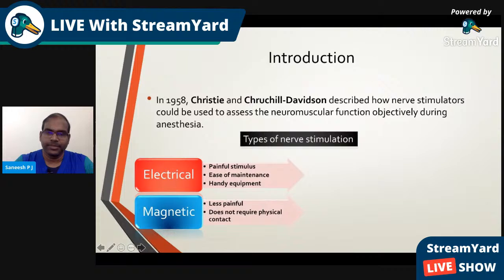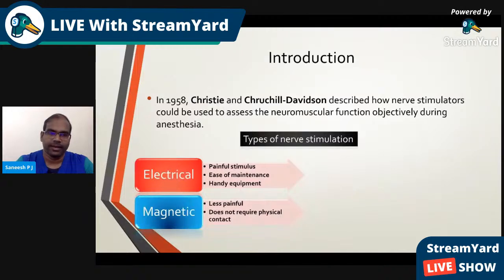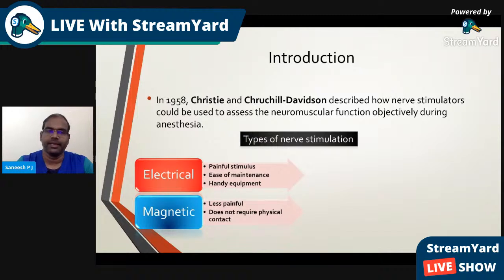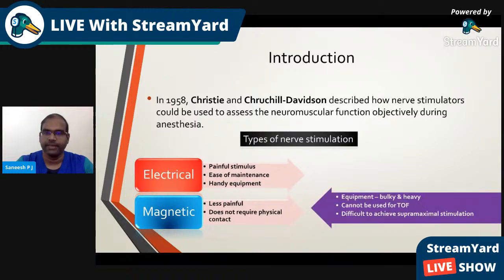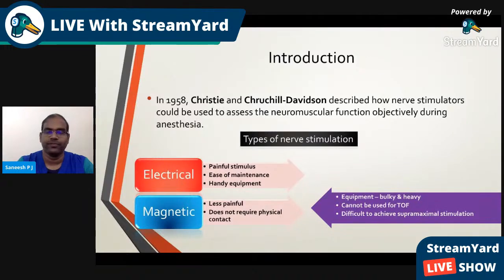The types of nerve stimulation, right from the time of innovation of nerve stimulators, are classified into electrical or magnetic methods. Electrical ones involve a painful stimulus, but the positive is ease of maintenance and the equipment is handy. Magnetic type of nerve stimulation is less painful, does not require physical contact, but the equipment is heavy and bulky, and it cannot be used for train-of-four.